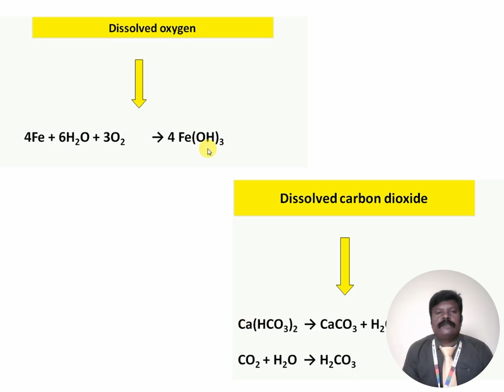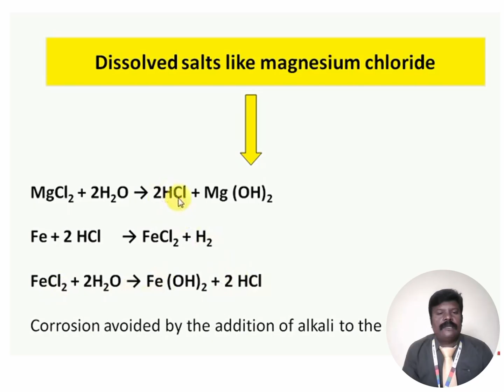Due to the presence of magnesium chloride. Yes, if the water sample contains magnesium chloride, it leads to boiler corrosion. The magnesium chloride undergoes hydrolysis in the presence of very high temperature and pressure, and converts into HCl and magnesium hydroxide. The boiler material reacts with the HCl and converts into FeCl2 and H2 gas, and the FeCl2 undergoes hydrolysis and converts into corrosion product.